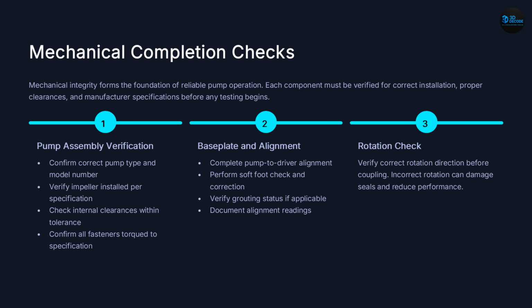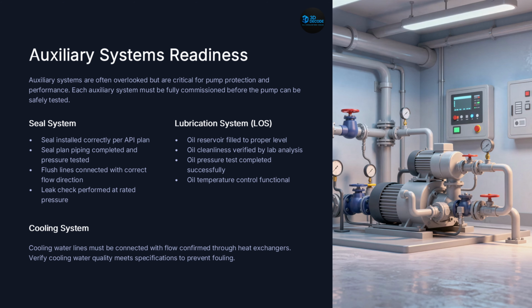Next comes rotation verification. Simple, yet critical. A wrong rotation direction can damage seals, reduce performance, and create confusion during startup, which means one of the simplest checks can prevent one of the most embarrassing failures. Experienced engineers never assume rotation. They verify it. Next, auxiliary systems readiness that quietly determines pump reliability.